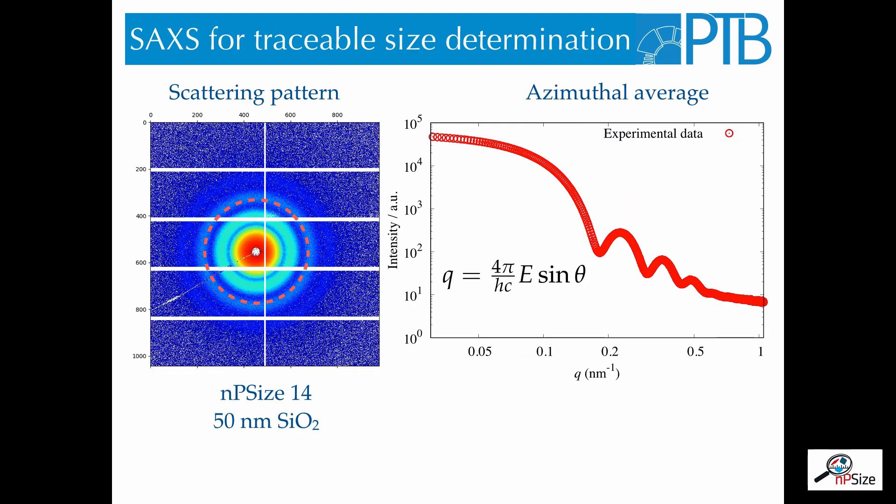On the left side, you see the scattering pattern that was collected from the NP-SIZE 14 material. This is a dispersion of 50 nm silica particles in water. The scattering pattern is circularly symmetric and after we collect the pattern, we average it over concentric circles to end up with a scattering curve, which you see on the right. The scattering curve displays the intensity of the scattered radiation as a function of q, which is the magnitude of the scattering vector and it is proportional to the sine of the scattering angle.